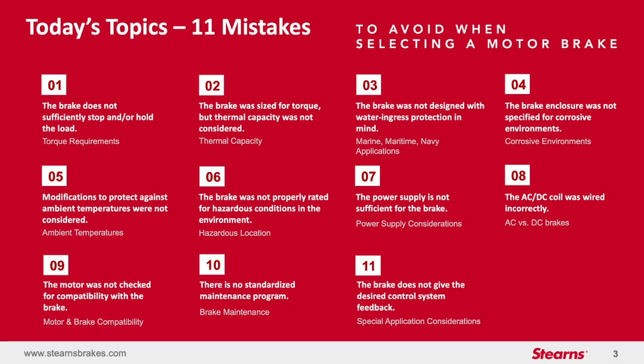So this will be our agenda for today. First, we'll take a look at torque requirements for assurance that the brake will efficiently stop and or hold the load, including full load motor torque, overhauling torque, average dynamic torque, and static torque calculations, followed by advice to better prepare for the thermal capacity required in rotational or linear load applications. Next, we will discuss the importance of understanding environmental and service conditions early in the brake selection process to ensure protection against corrosion and rust.